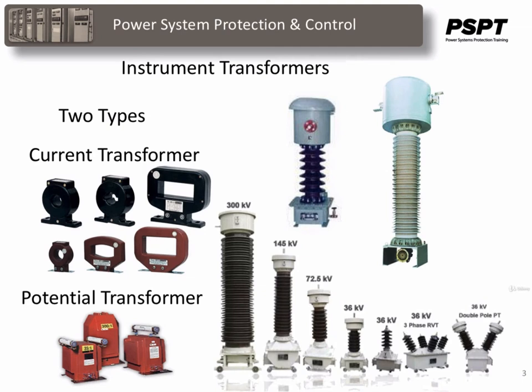Potential transformers or voltage transformers are used for a similar purpose, and that is when the voltage of the AC circuit exceeds 750 volts, as it is not possible to provide adequate insulation on measuring instruments for that voltage level. Then the potential or voltage transformer is introduced into the circuit so that the voltage to the instrument can be at a safe level. And just as there are various voltage ratings on a current transformer, there's also various voltage ratings on a potential transformer.